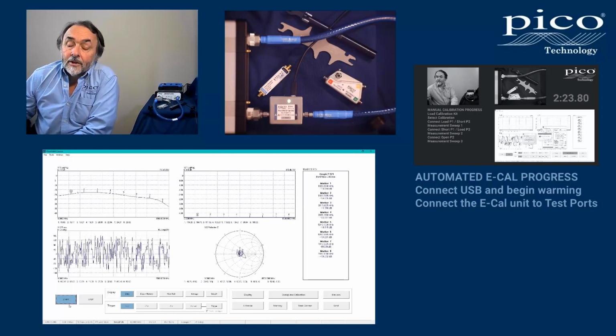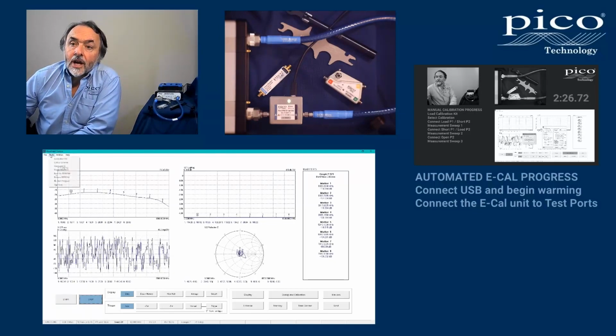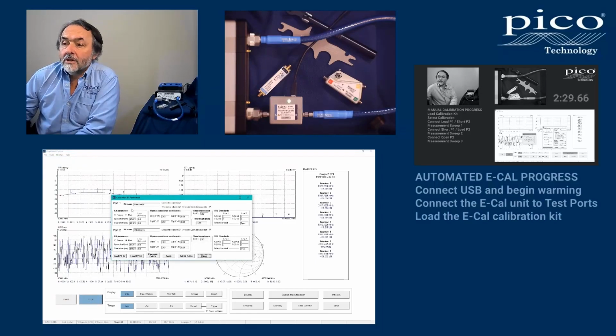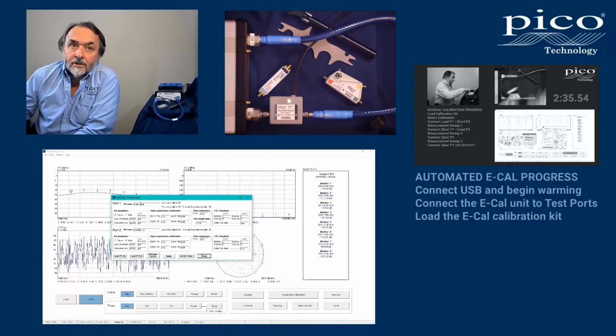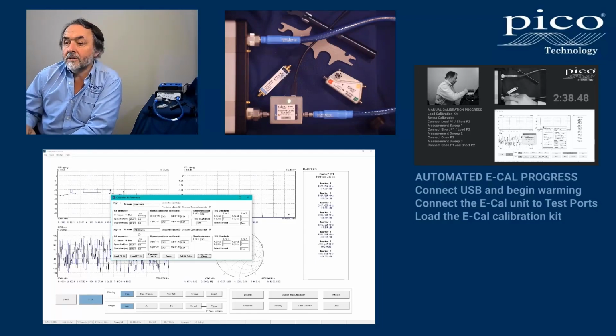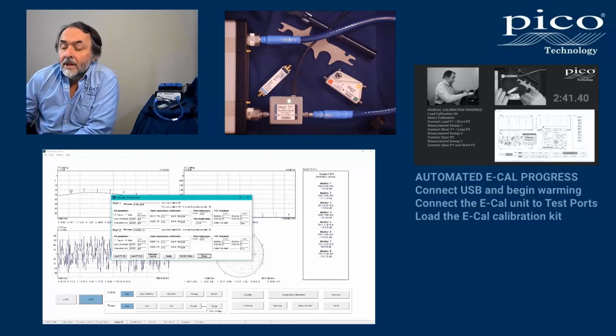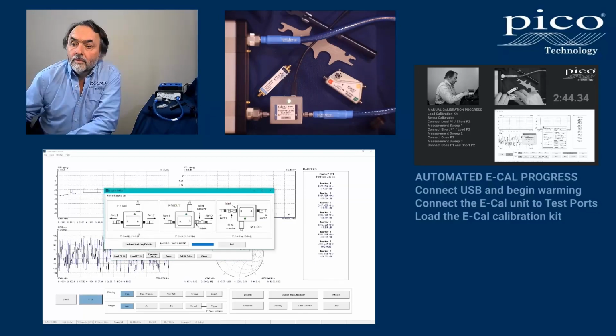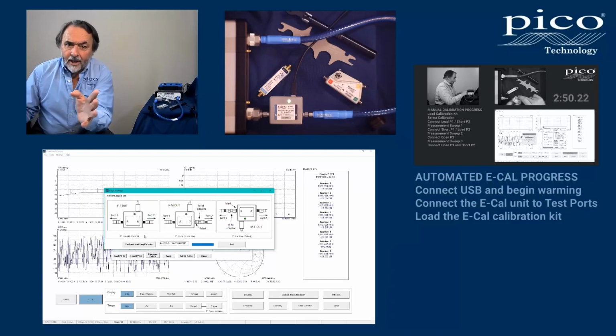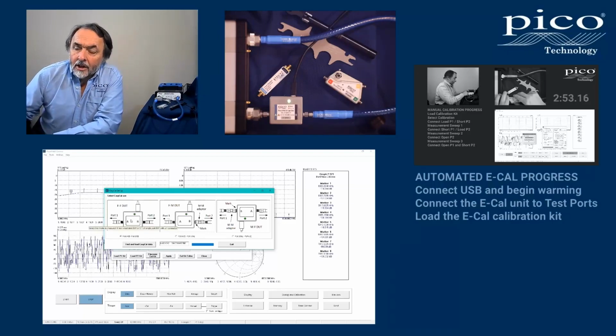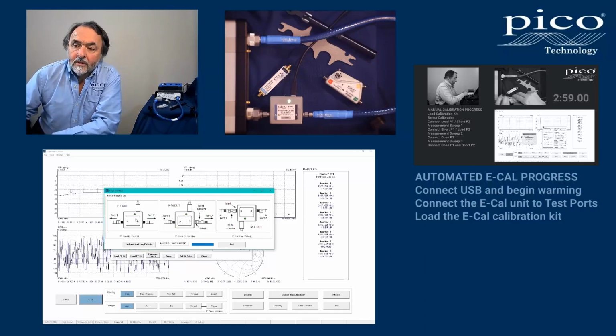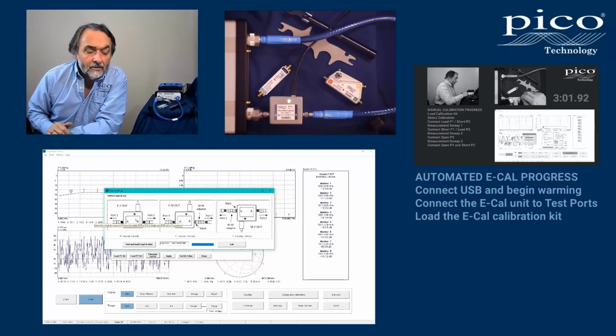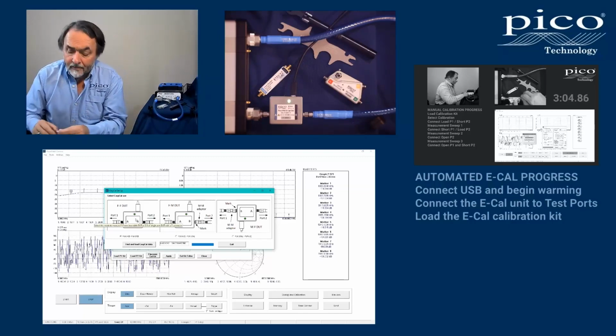So here we are. Our first action is to check the calibration kit that is loaded to the ports, and you can see this is not an eCal module that is loaded to port 1 and port 2 at the moment. So let's select electronic cal kit. So if we recall the connections that we made earlier, I connected port A to port 1 and I connected port B to port 2. So we're going to be using this interconnection detail. But I will just mention these other two.